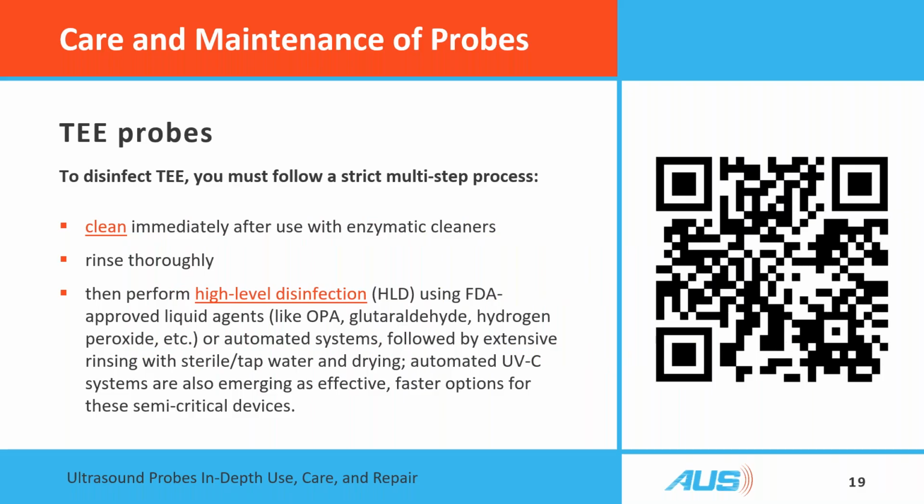But you need to absolutely follow a strict multi-step process. You have to clean them immediately after with enzymatic cleaners. You have to rinse that thoroughly. You can't leave that on the probe. It causes degradation. And then you have to perform high-level disinfection using the FDA-approved liquid agents. We've listed some there. There are automated systems out there that you can use. The hospital can purchase, and they do it all for you.